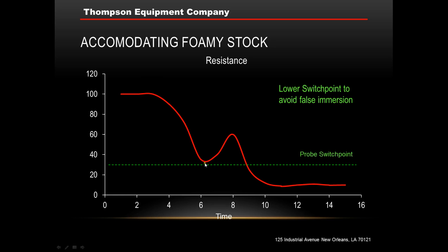What we would like to do is discriminate against false immersions as best we can. The best way to do that is to basically drop the switch point — try to drop it below these false immersion swings in resistance. Once you do, you try to find out what this low level is and then set your probe switch point somewhere between that and the actual immersed level. That's pretty much a straightforward way to do it. I've written a white paper on it, which is available through the Thompson Equipment Company website.